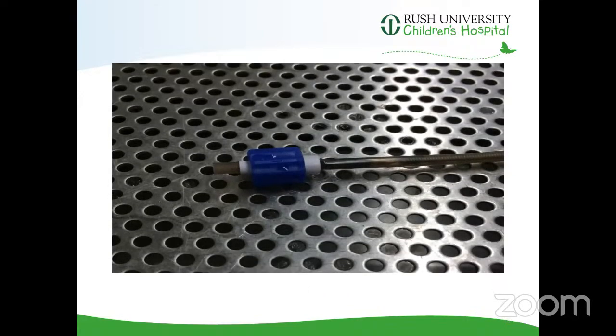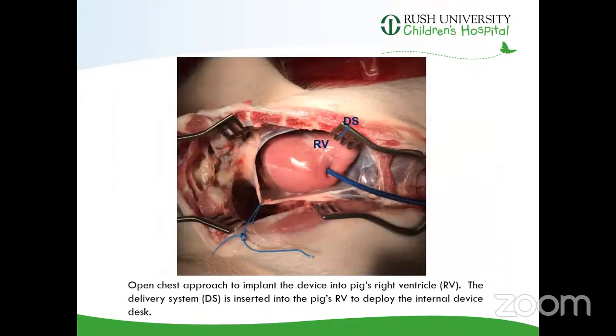This was the cable mounted with the atrial septal occluder device shell without the electronic circuit. And that was applied to the RV wall of a pig. And you can see here that the delivery cable is inside the right ventricular wall. And in this picture, the internal disc was already deployed.